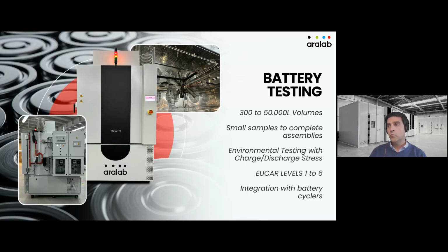Usually EUCAR levels from 1 to 6 are available, and usually these chambers are also integrated with battery cyclers that ensure the test from the battery supply point of view.